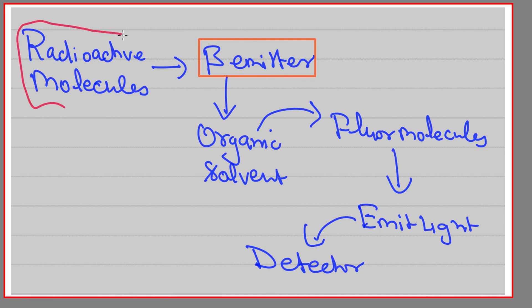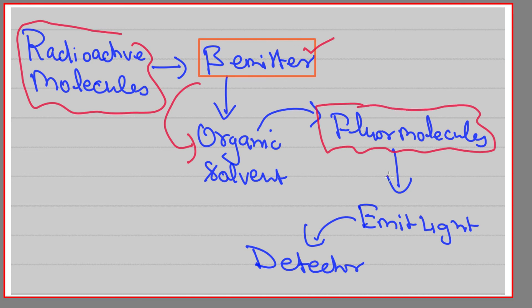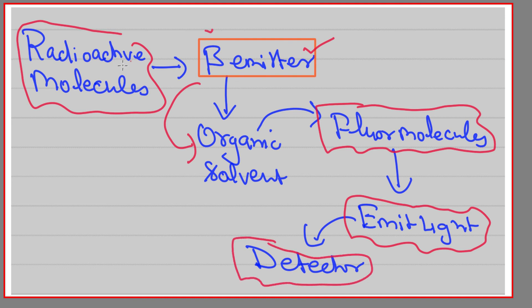In a simplified way: your radioactive molecule, which can be a weak beta emitter, emits radiation with some energy. This energy is captured by the organic solvent, which transfers it to the scintillators or fluor molecules. The fluor molecules enter an excited state and upon returning to the ground state emit light, which is detected by the detector. More radiation means more light emitted, so this way we can quantify how much radioactive element is present in a sample.